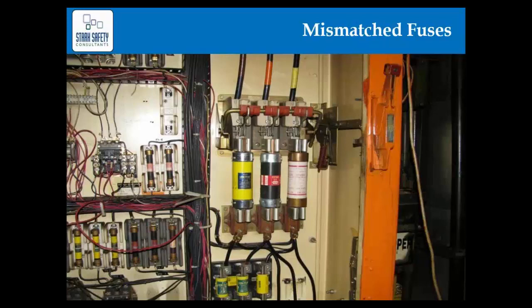Without consolidating fuses, it's very difficult to know which phase an arc could potentially start on, and it's rarely practical to run multiple scenarios for every device. The only alternative we've found is to model it as a non-fused disconnect, noting that it's due to mismatched fuses. This shows no protection, which could be seen as a conservative approach, but it also means you can't do an accurate coordination evaluation. That's another assumption that could hurt the accuracy of your evaluation.